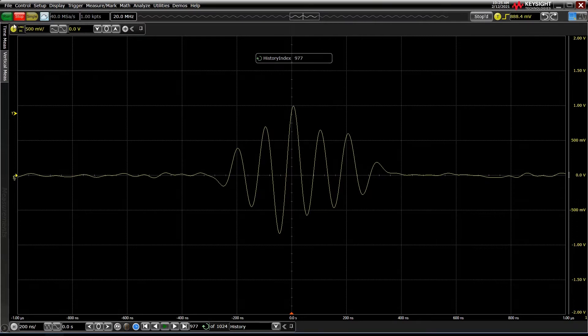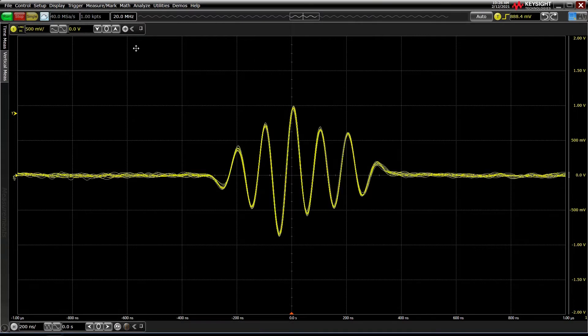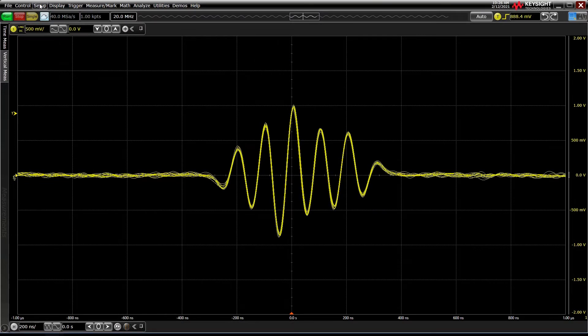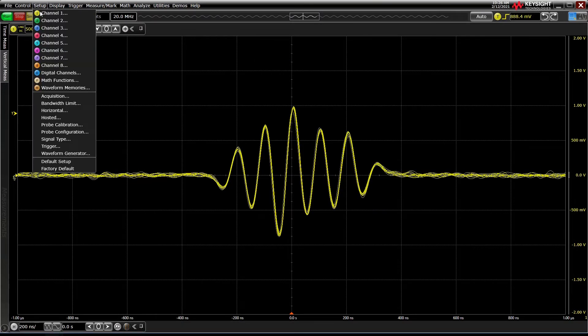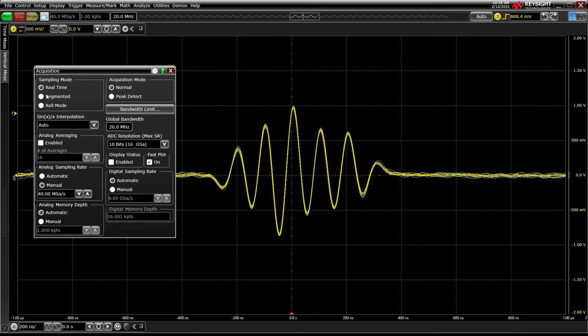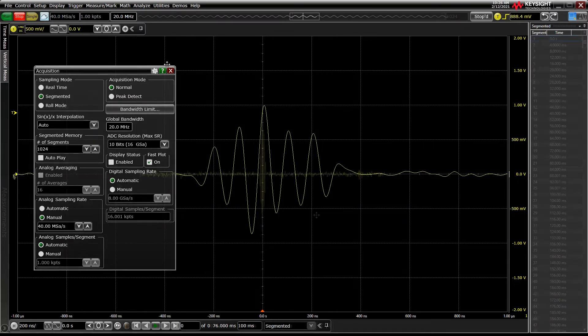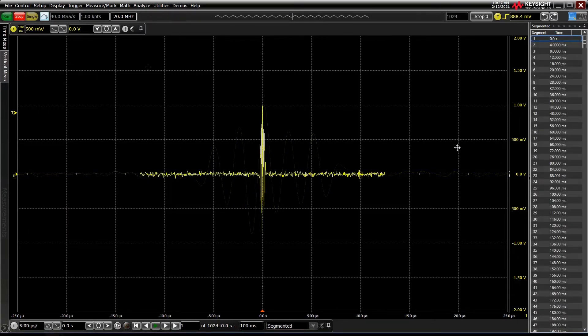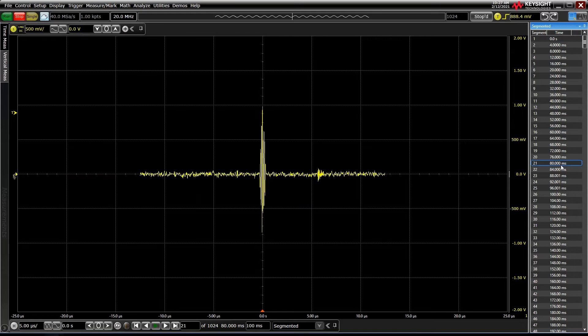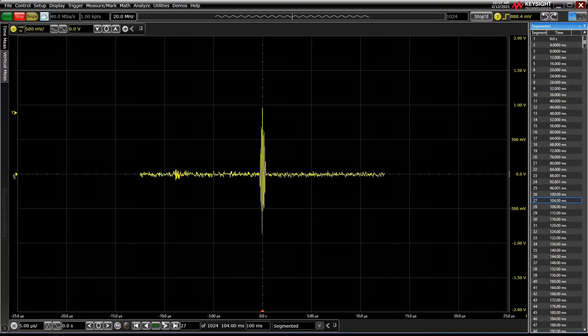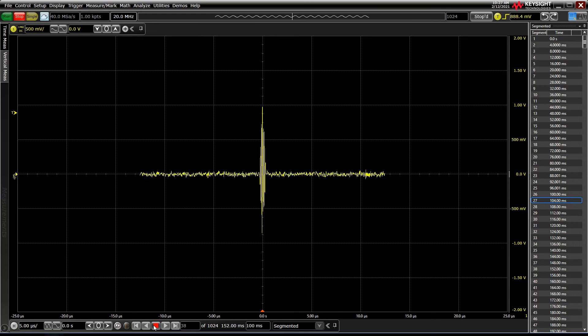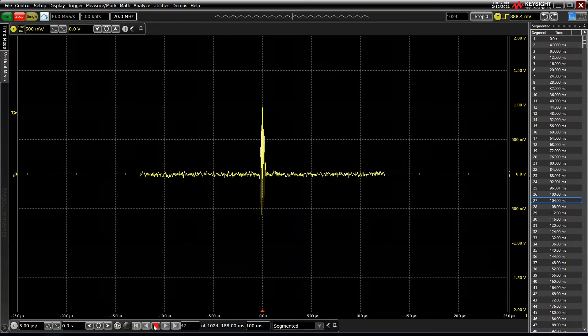Alternatively, we can set up a forward-looking segmented memory capture. This acquisition mode dynamically turns off acquisition when no trigger events are present, and turns acquisition back on when a trigger event is found. What you are left with are tens of thousands of sequential trigger events that you can navigate through. Each one is time-tagged, and there are various ways to navigate through and display this data.